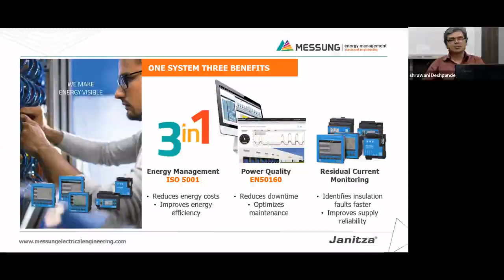First, that is the PCC, the point of common coupling, where the incoming power comes to any premises or any company. There you can connect these meters, that is UMG 512. Then the main distribution system, then the sub distribution system, then the machine building centers, and the sub measurement, that is the load centers, where the actual consumption is. There you can connect these meters.